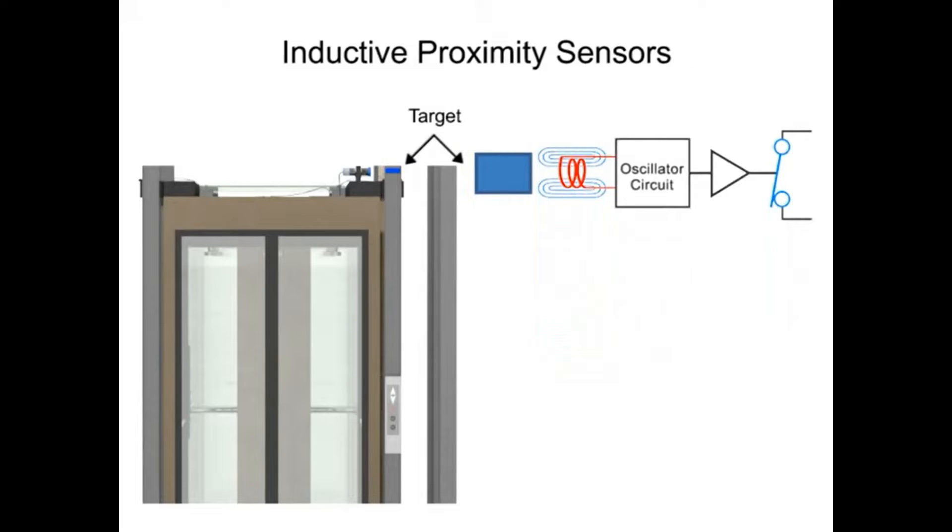electrical currents known as eddy currents are induced on the metal surface. These eddy currents induce a power loss within the oscillator circuit, and in turn cause a reduction in the amplitude of the oscillations. This is known as the ECKO, or eddy current killed oscillator, principle.